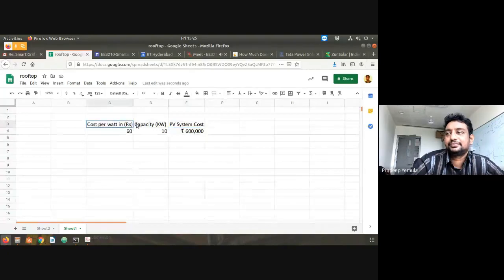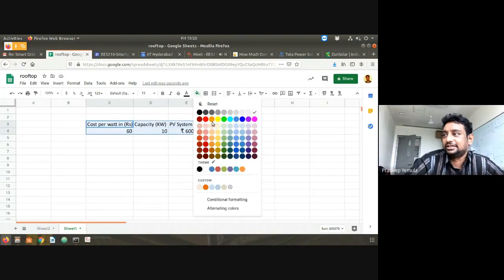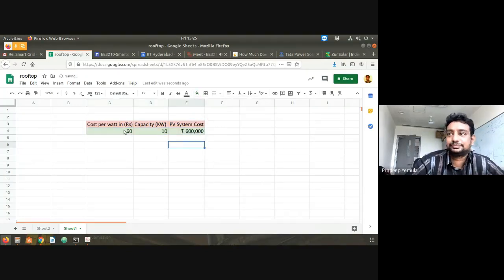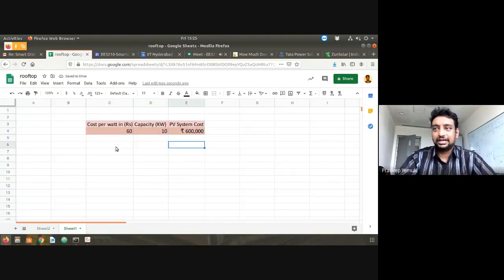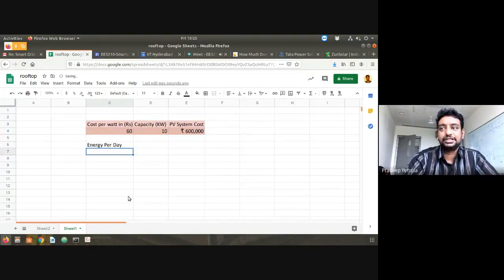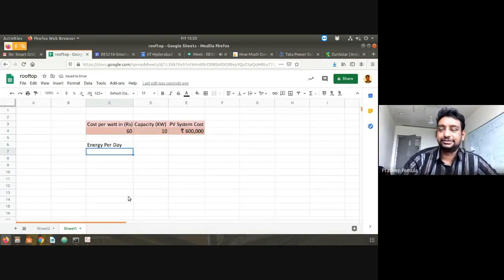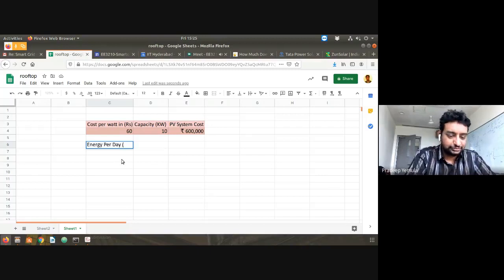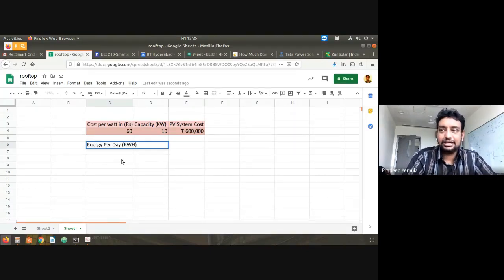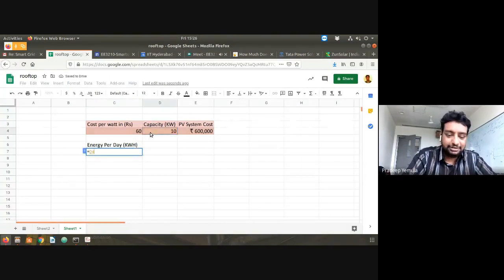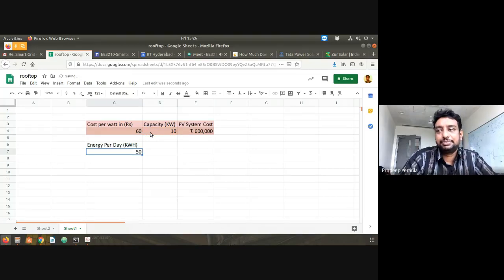Now what about benefit? Let's calculate the benefit. Energy per day — how can you calculate energy per day? The thumb rule is: if you have a 1 kilowatt system, it will generate 5 units. So for a 10 kilowatt system, simply multiply by 5 — you can generate 50 units per day.